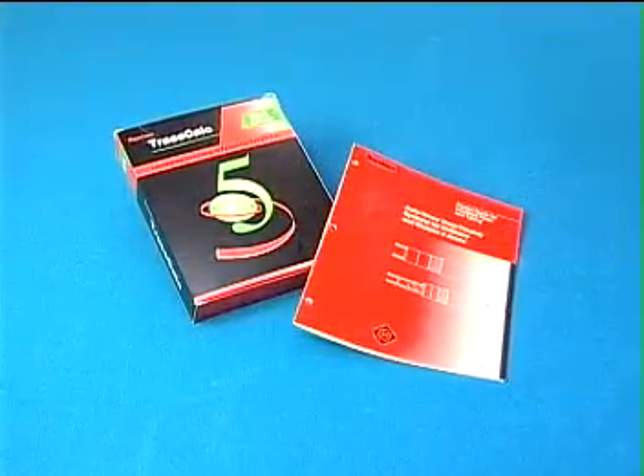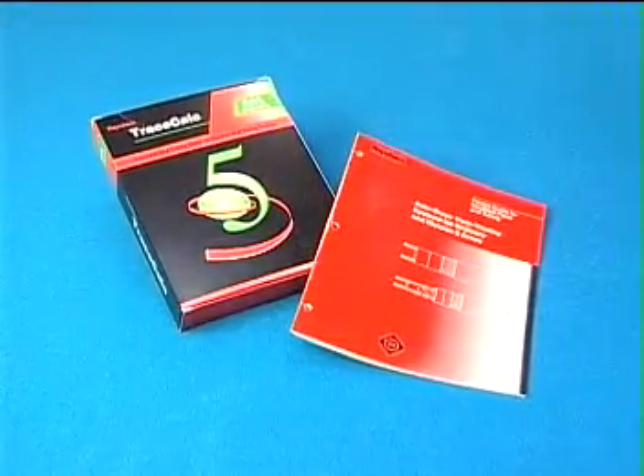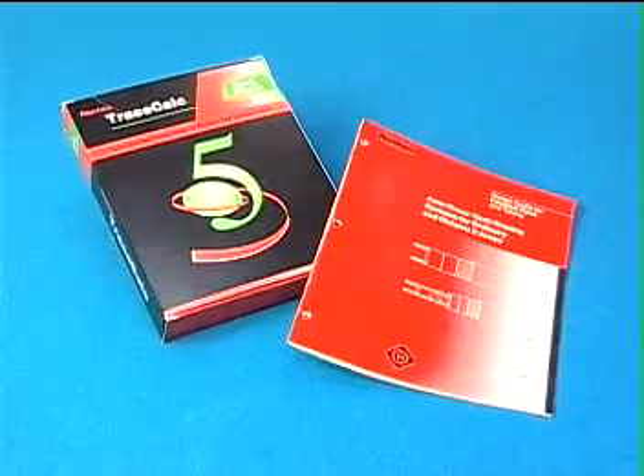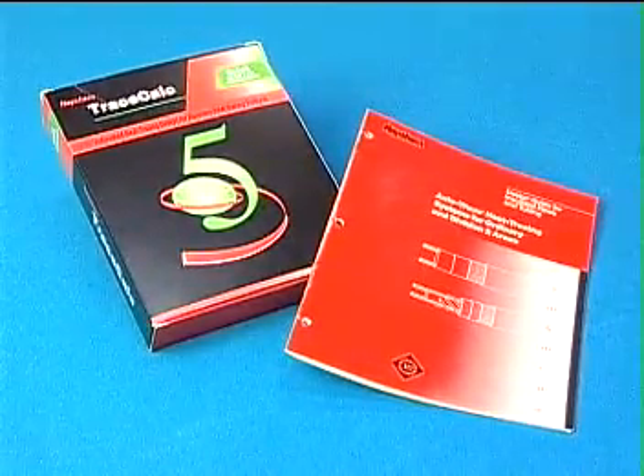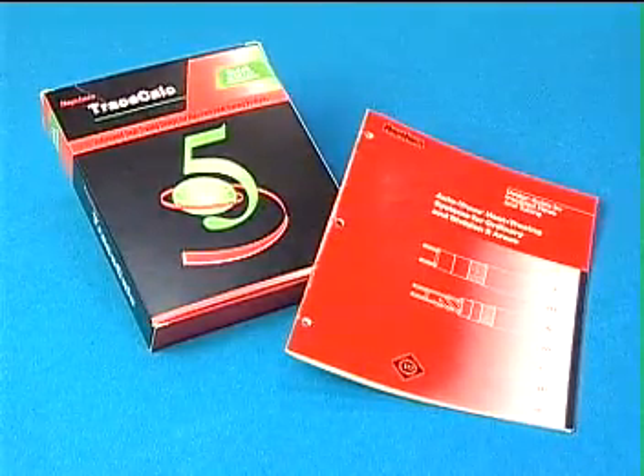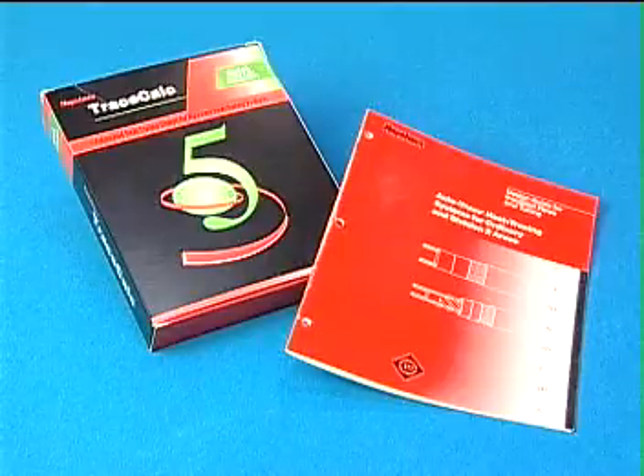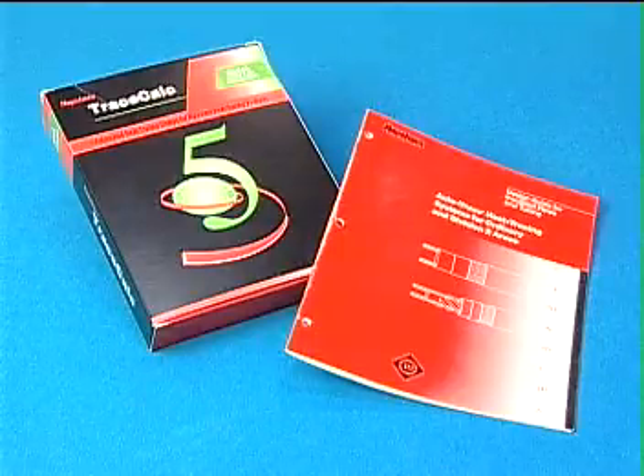The electrical design of the system, including electrical protection and circuit breaker sizing, is determined by using the TraceCalc design software or the design guide. Always remember to follow the applicable electrical code requirements when installing the system.